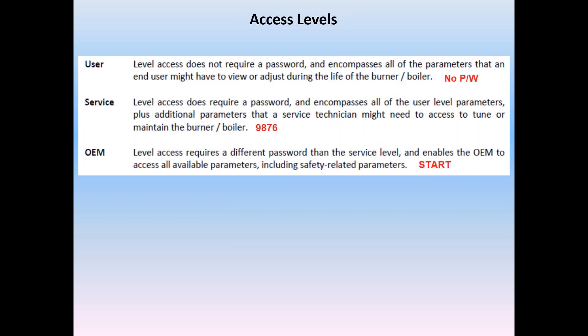On the first page of section three, we defined three access service levels of the LME-5. This is necessary to enable users to be able to get into and adjust set points, service technicians to be able to adjust fuel curves and OEMs to program configuration settings. User level doesn't require any password. Service level factory default is 9876. And finally, OEM factory default is START. It's all caps and case sensitive.